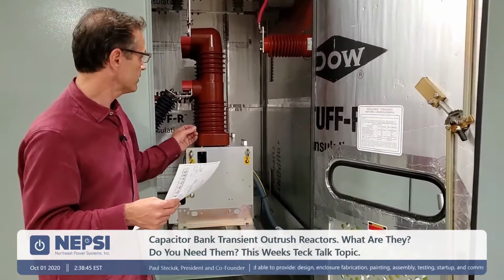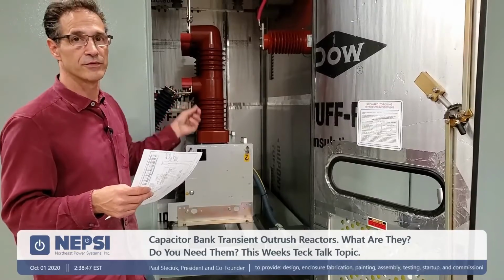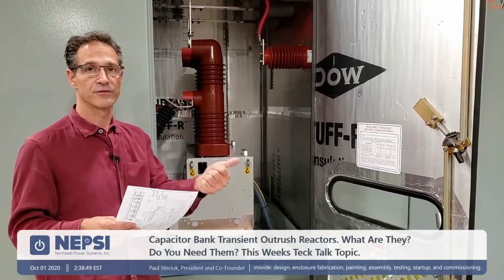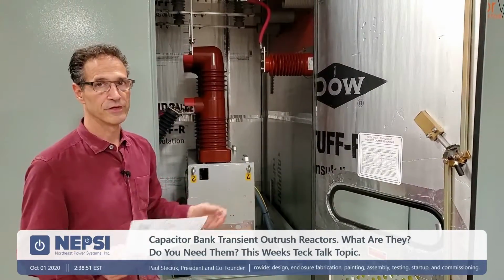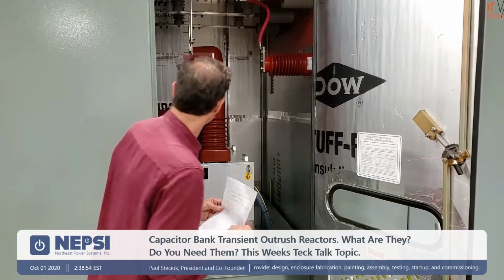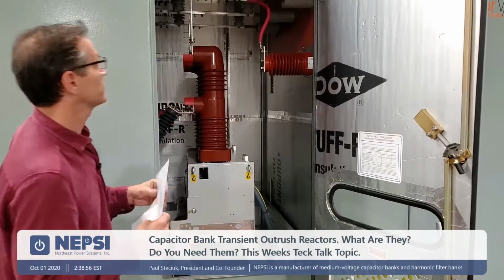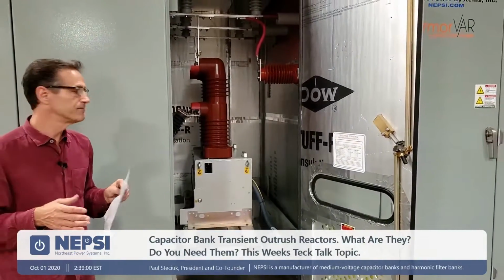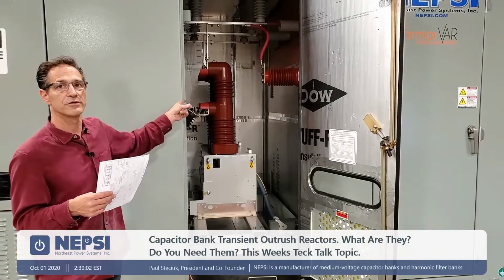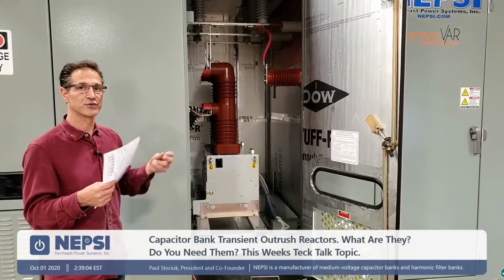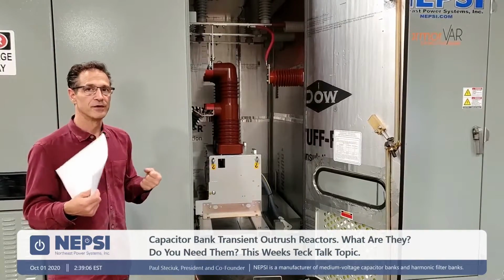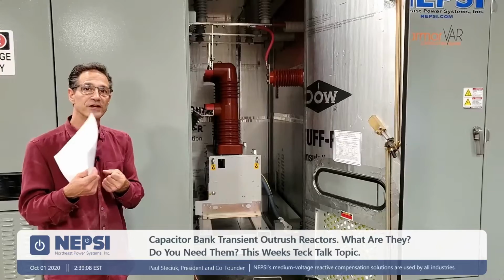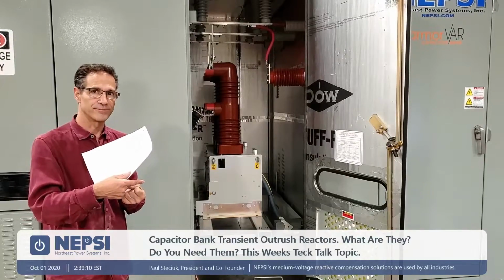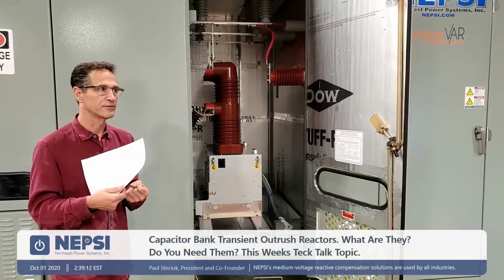And incidentally, we designed these compartments so they will house both a Southern States cap switcher or a VD4 CS. So that's really the essence of this I wanted to talk about for a moment, because it's still a relatively new device. Remember, it's got a short circuit interrupt rating, which you can use to eliminate the feeder breaker to the capacitor bank. So it's a cost-saving device.